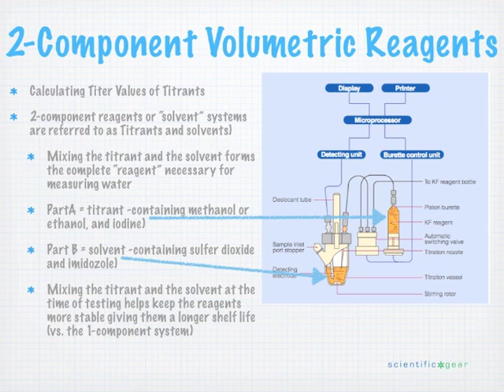When we look at the Karl Fischer reaction mechanism, it's actually a two-step reaction. In the first step, we are reacting methanol with sulfur dioxide, which forms a methyl sulfurous acid that needs to be neutralized. When we neutralize that with the imidazole base, we produce an alkyl sulfite intermediate complex, which takes part in the second step of the reaction. So with our two-component solvent system, we added sulfur dioxide and imidazole to the methanol normally used for titration. The titrant is simply a solution of either methanol or ethanol and iodine. If we tried to use the titrant with ordinary methanol, nothing would happen, because it's missing the sulfur dioxide and the imidazole.